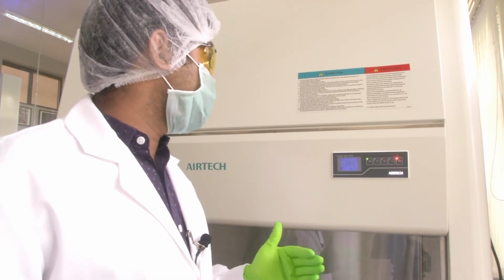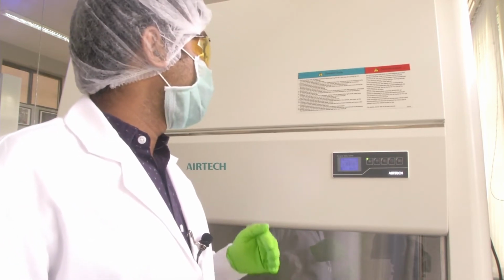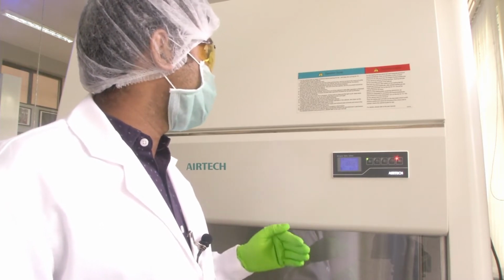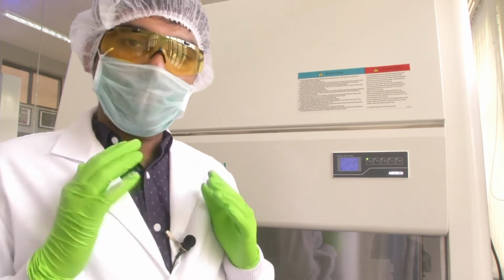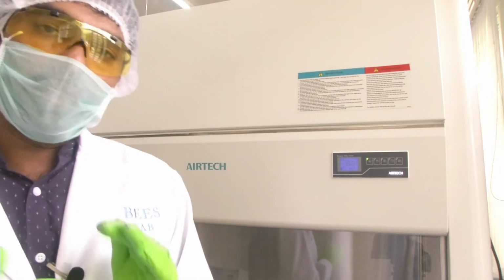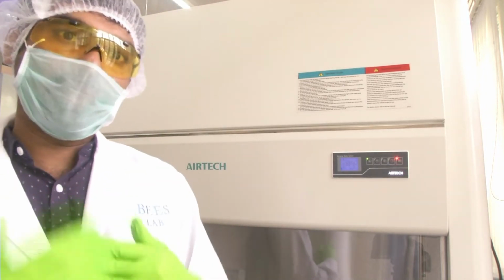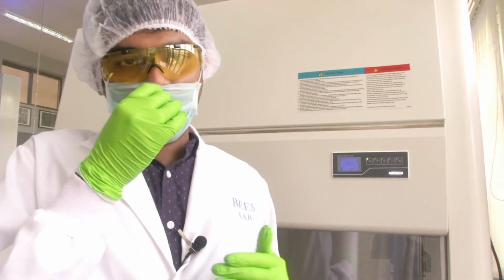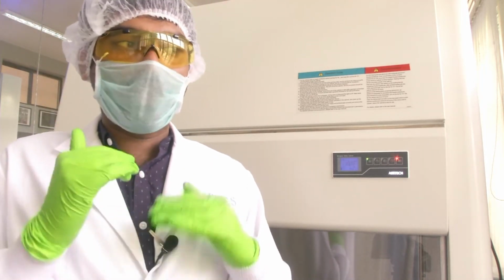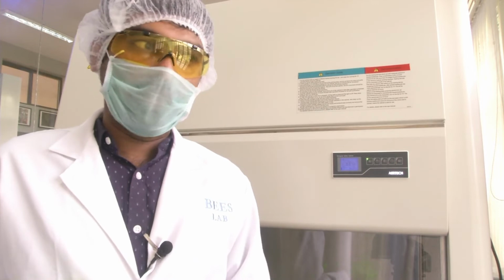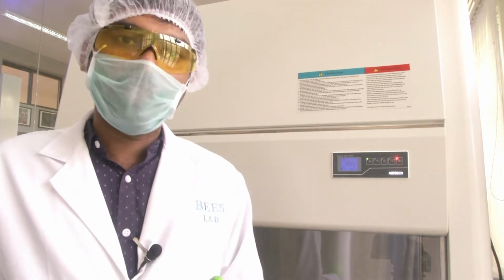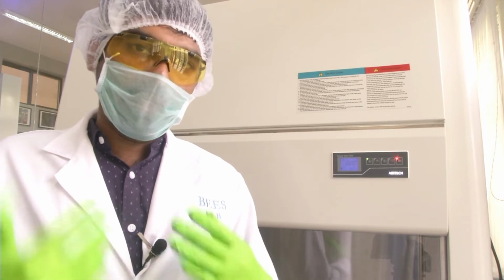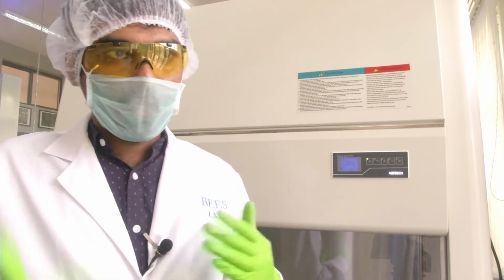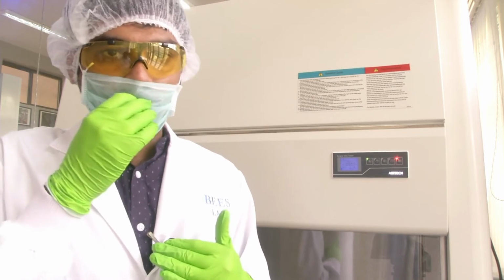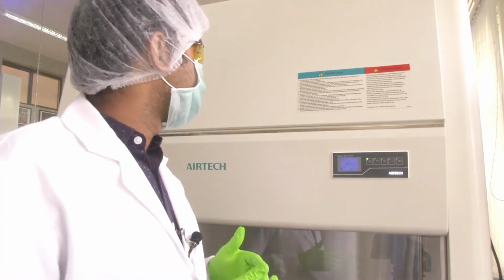Choose proper disinfectant according to the articles operated in the cabinet and clean up the residuals of the disinfectant with clean water in time. So it is very important that we use very clean water, preferably distilled water or DI water, which is even better, which is called deionized water. Such water will have no ionic content in it, so it will not be reactive even to a very small extent. By default water is also not that reactive, but it will still have a lot of dissolved salts and ions in it. So we have to use deionized or distilled water, so that any unknown ions dissolved in the water don't react with your sample or your cabinet.